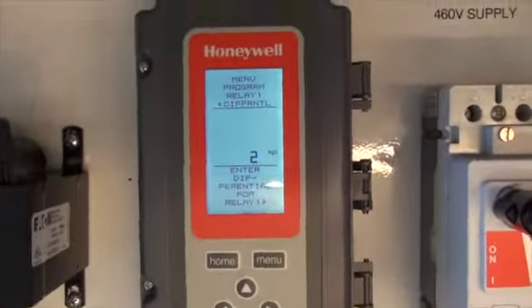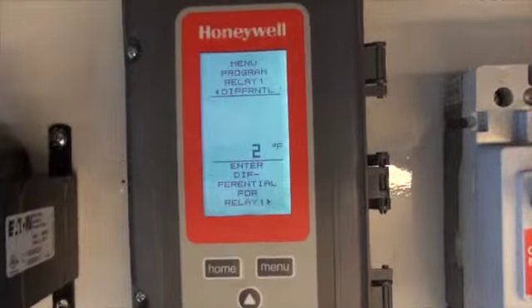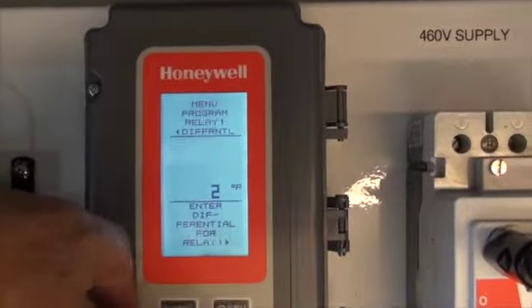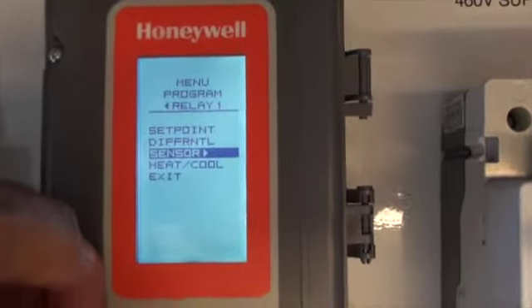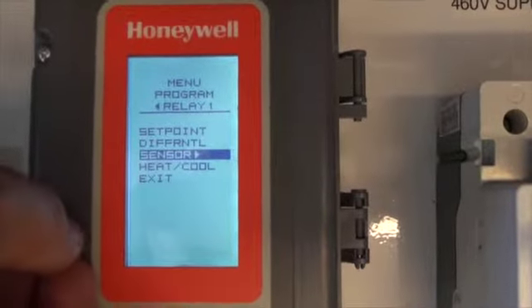It's an open tower situation. It's good to have a spray pump. You have to have the spray pump come on before the fan motor. Anyway, I'll set the differential at 2 degrees for the spray pump. Press the right arrow key to move it down through the program.